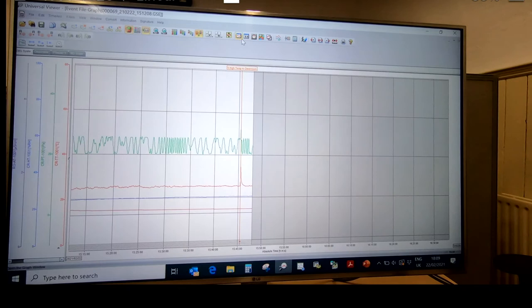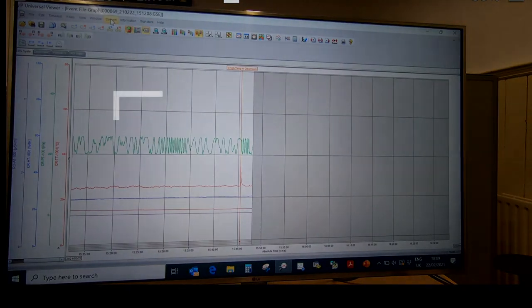The other important thing to note is in terms of the data file itself, every data file that's generated with the advanced security function for 21 CFR Part 11 compliance has the configuration file embedded behind it.